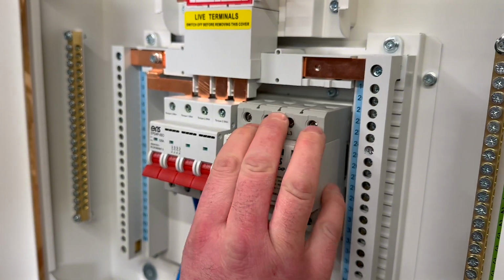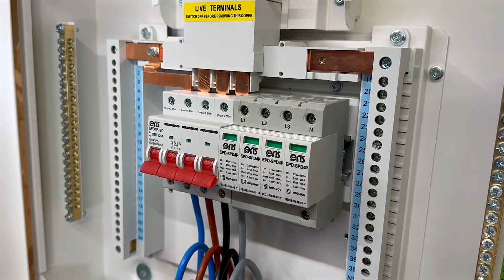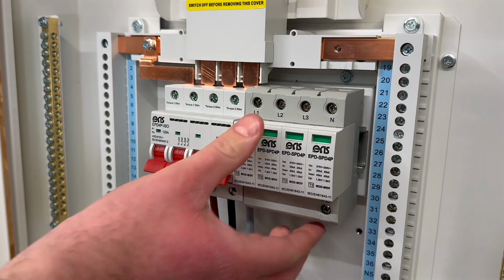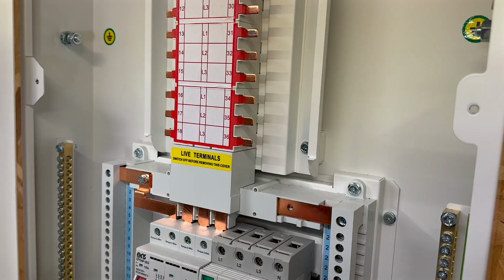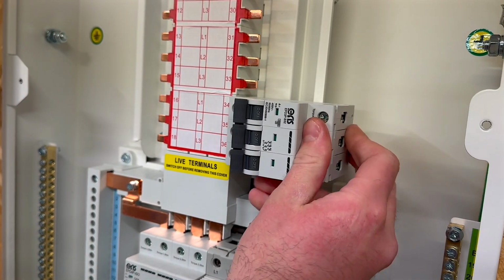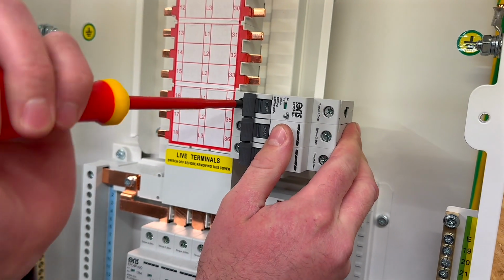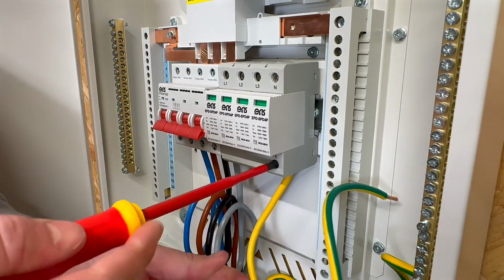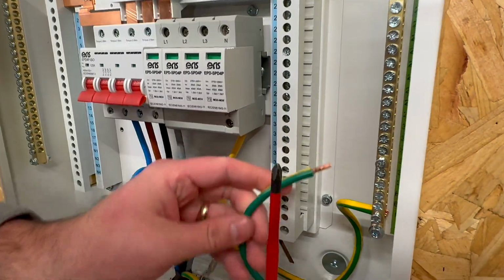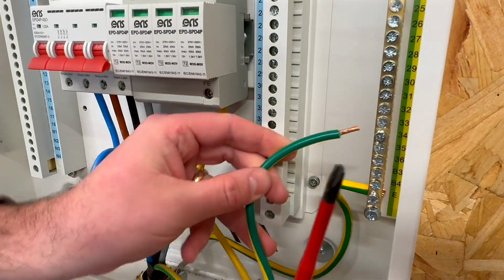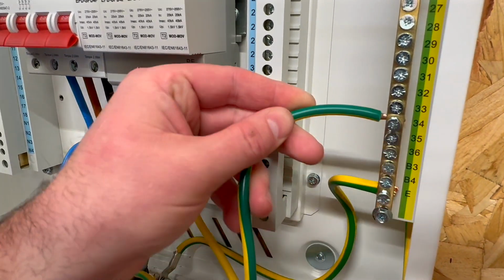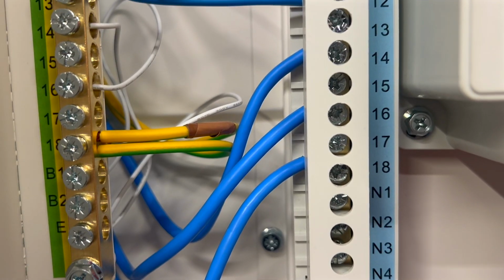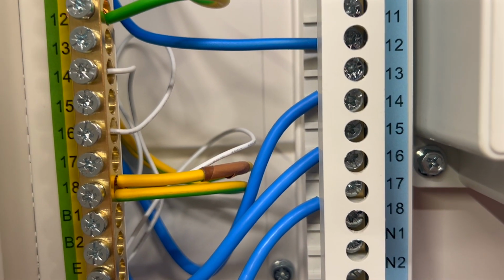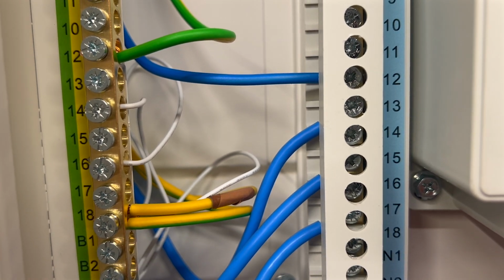Next to the main switch is a dedicated position for installing a surge protection device, SPD. The installation process requires connecting the SPD to an MCB in one of the outgoing ways, ensuring protection when the device reaches the end of its lifespan. The SPD must also be connected to the earth and neutral bars. Minimizing the length of the earth connection is crucial to ensure optimal performance during a surge event. The neutral and earth bars are numbered to correspond with the outgoing circuits, simplifying testing, inspection and maintenance.